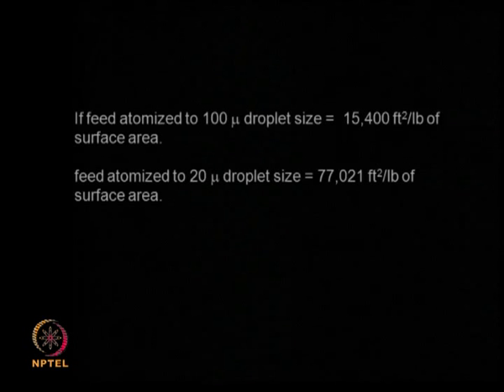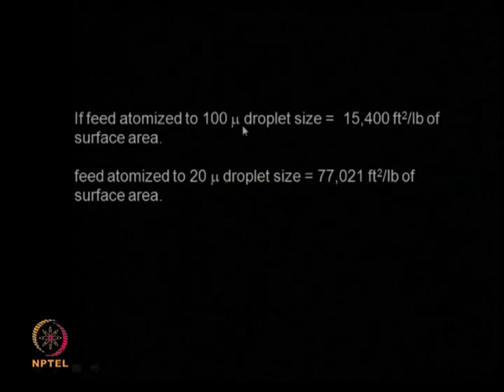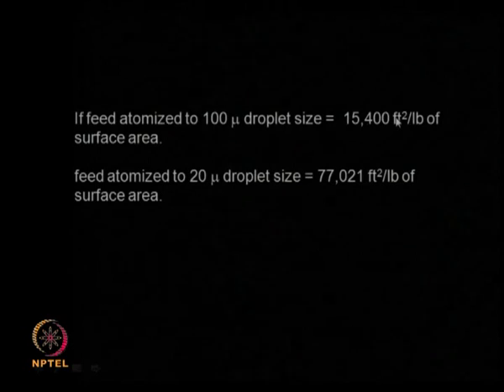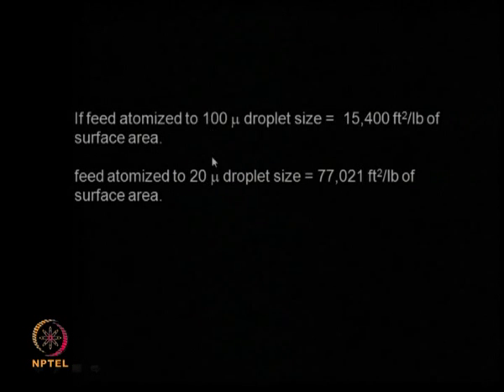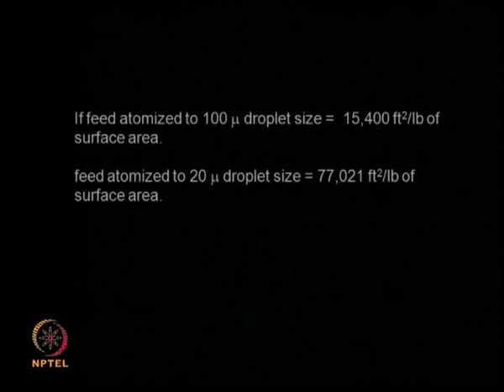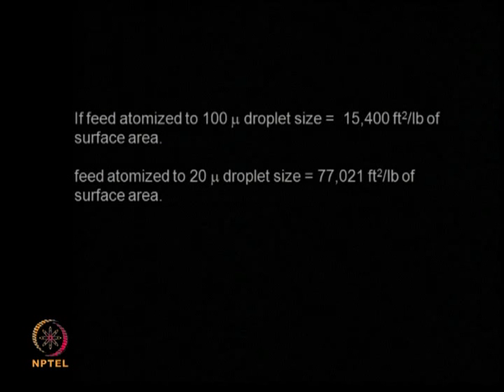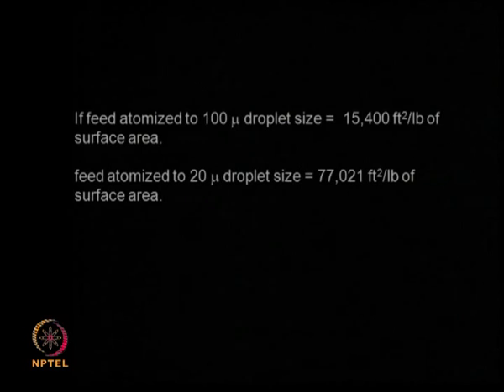The beauty of spray drying is that finer the particle, higher the surface area per unit volume, so heat transfer is good and drying takes place very fast. Solubility also increases because of very high surface area to volume ratio. For example, atomizing to a 100-micron droplet size gives 15,400 square feet per pound, whereas reducing to 20 microns gives almost 77,000 square feet per pound — raising it by almost a factor of 5. That is the main advantage of increasing surface area by reducing particle size.